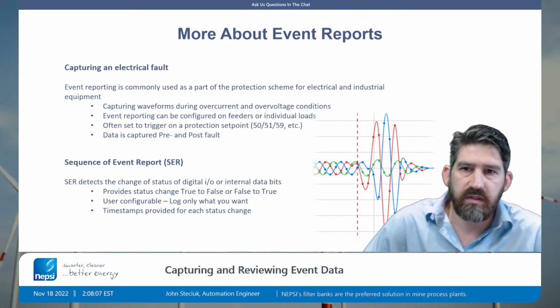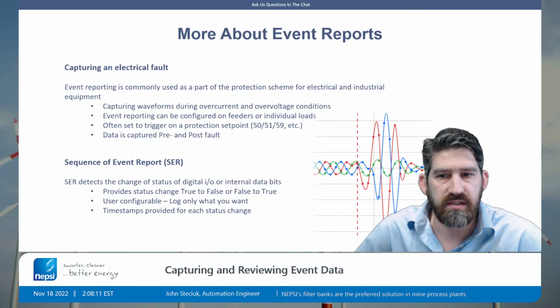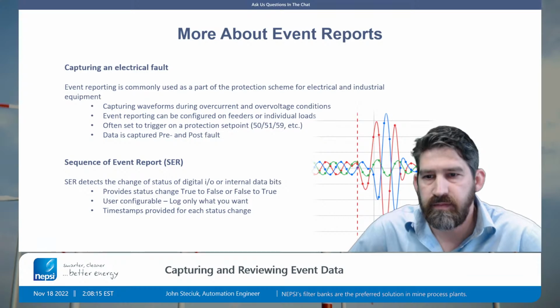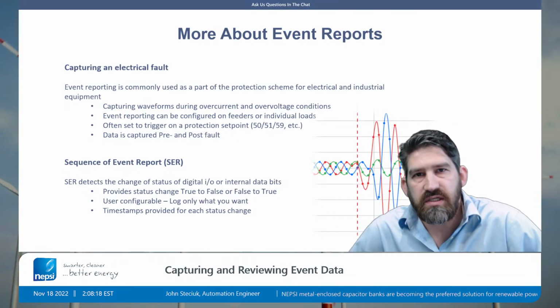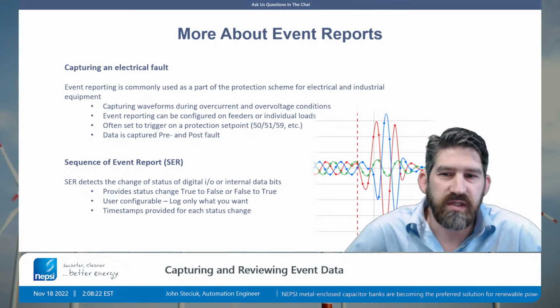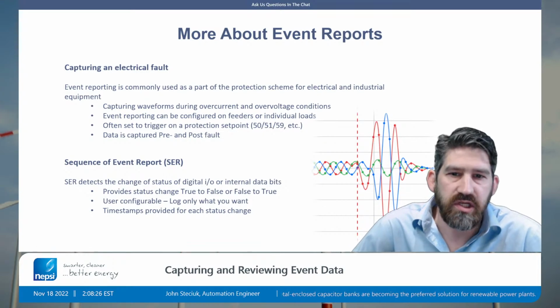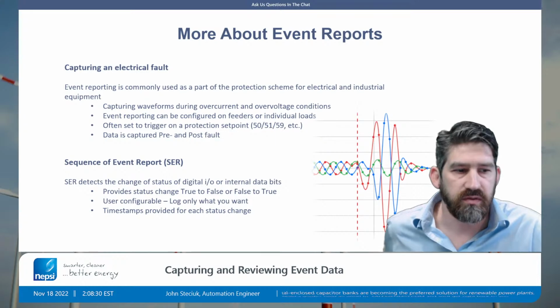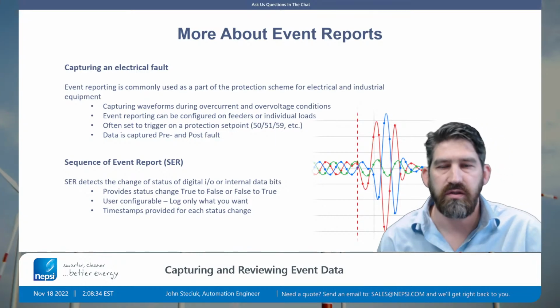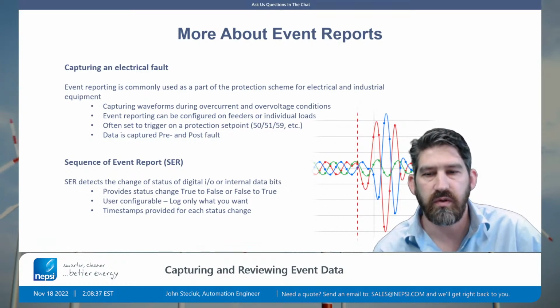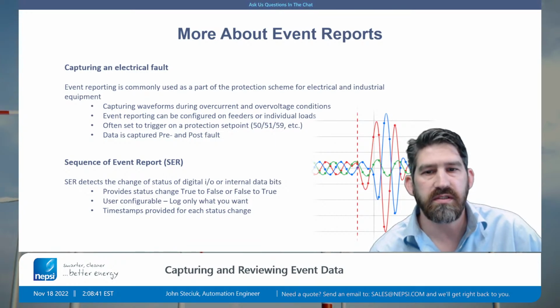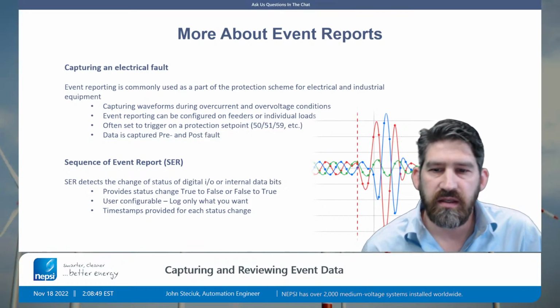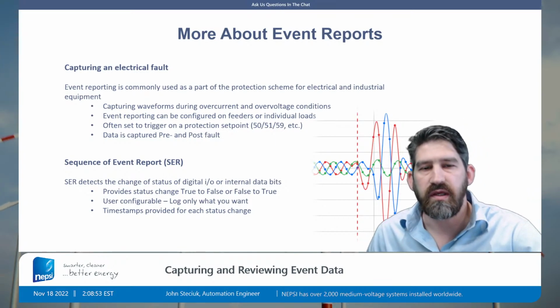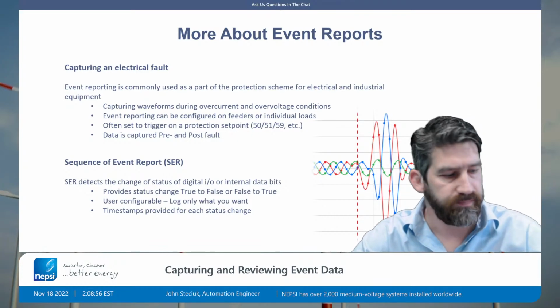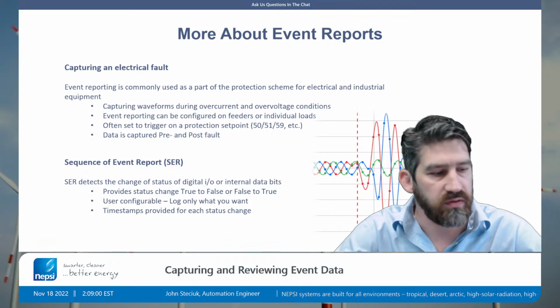So another type of event reporting, specifically in the SEL relays, is a sequence of events report. The sequence of events detects changes in the status of digital inputs, outputs, and internal data bits, and provides a record of status changes from true to false or false to true. And you can configure which points you want to record. You can exclude points if they're chattering or operating more than expected, filling up your log. And all these points are time-stamped so you can see exactly when they happened. It's pretty useful when you're troubleshooting during commissioning or any other point.